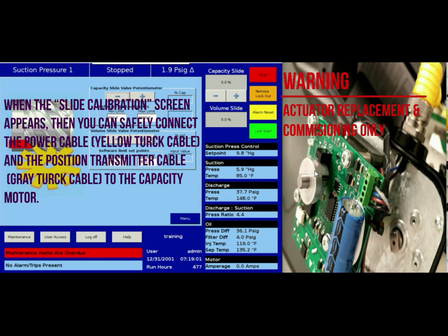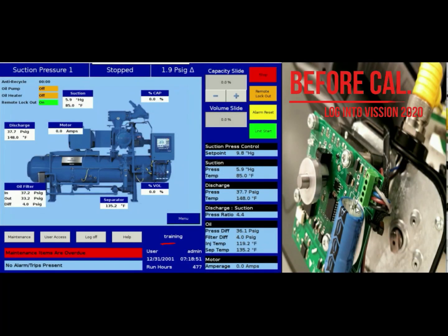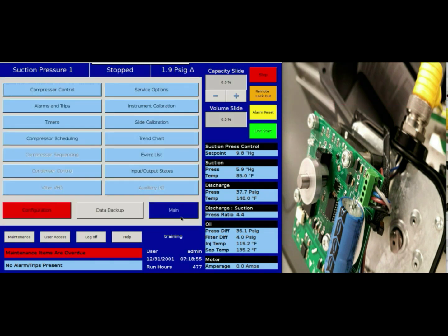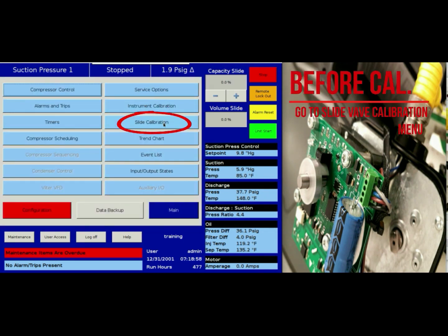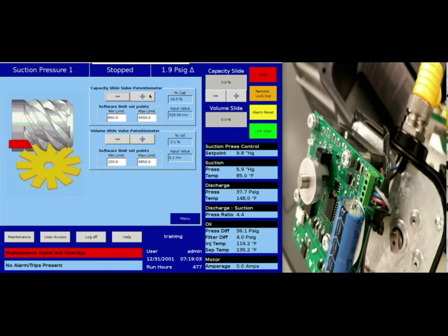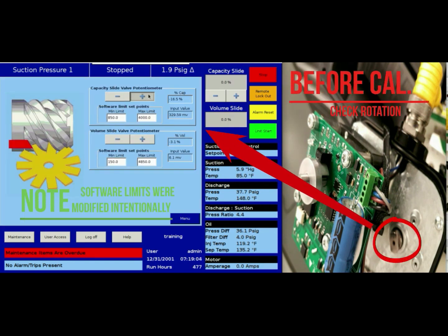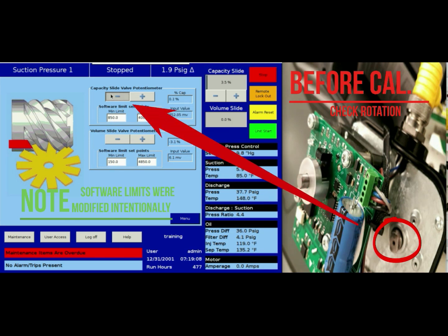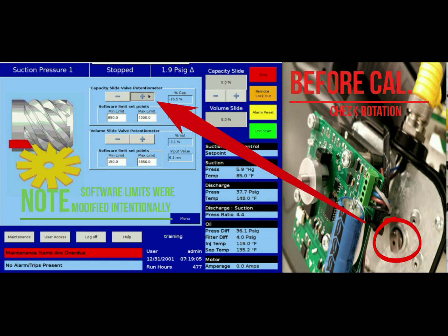To start the calibration process, you must log in as admin or level 3 user. Once successfully logged in, you can go to the main menu and select slide valve calibration. Once in the screen, it is now safe to connect the power wires to the actuator. After doing so, you can press the minus and plus buttons on the actuator you are calibrating to check the correct command shaft rotation.